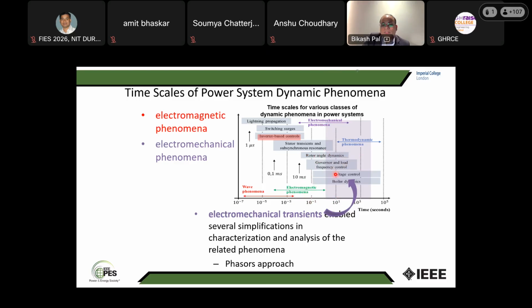Then you have governor load frequency, the voltage control, then the boiler dynamics. They're all long term dynamics, and the time is larger, hours. So they're thermodynamic phenomena, but I'm not going to discuss them because I want to focus on the oscillation control. But then you see there is a stator transient, which is about 50 hertz. Then suddenly something has come, called inverter based control, which is very fast oscillation. So this is the electromechanical phenomena that we are talking about.